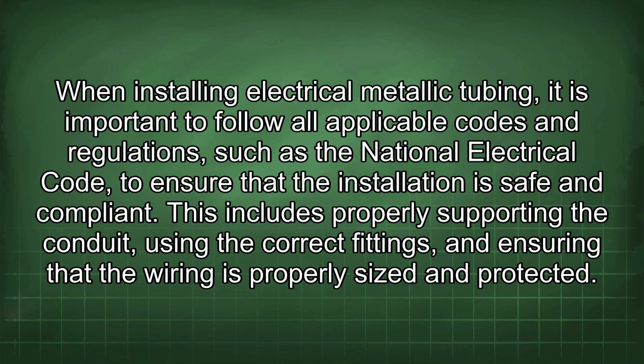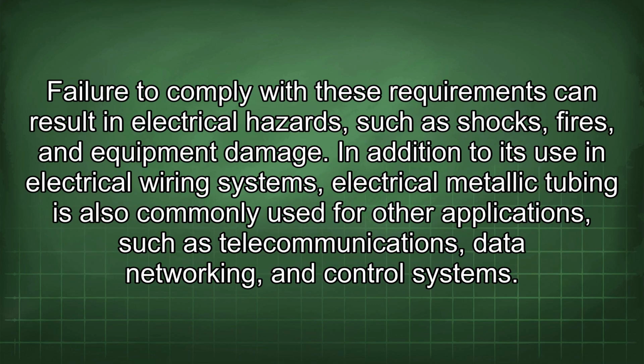When installing electrical metallic tubing, it is important to follow all applicable codes and regulations, such as the National Electrical Code, to ensure that the installation is safe and compliant. This includes properly supporting the conduit, using the correct fittings, and ensuring that the wiring is properly sized and protected. Failure to comply with these requirements can result in electrical hazards, such as shocks, fires, and equipment damage.